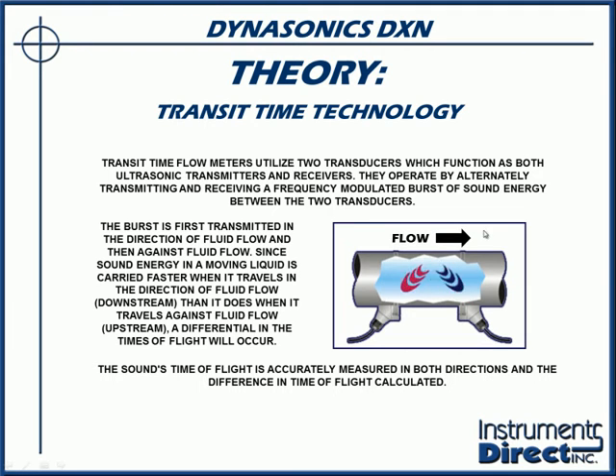As you can see, the flow is going from left to right. The sensor on the right-hand side also blasts a sound burst across the pipe, reflecting off the back wall to the sensor on the upstream side. The differential between these two, because the flow is going from left to right, is the coefficient we use to derive how fast the liquid is going inside the pipe. The faster the flow rate, the greater the differential.